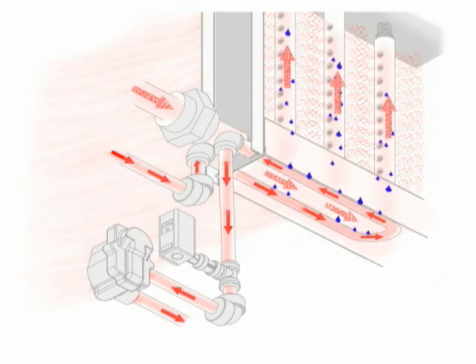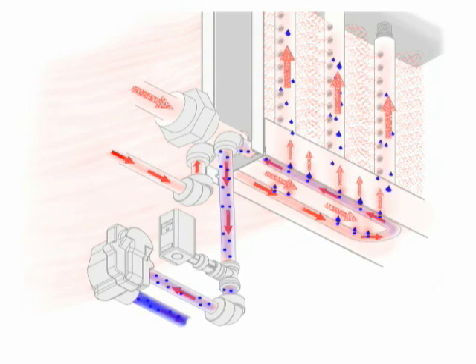Simultaneously, while dispersion tube generated condensate falls to the heat exchanger and gets vaporized into humidification steam, an equal volume of pressurized condensate forms in the heat exchanger and exits to the condensate return main.